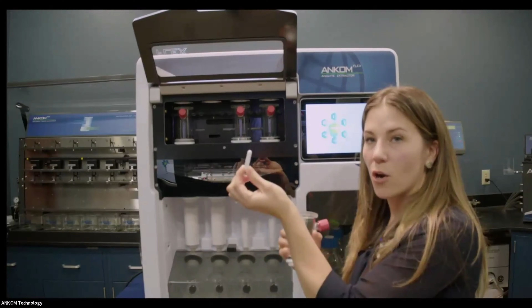Your filter would go in the bottom of this digestion vessel. You would weigh your sample, and just slide it in place. These ports are for, in particular, vitamin analysis. You can add an internal standard. These tops come down and seal the tops of your vessels. And the instrument is going to do a pressure check and make sure you have no leaks, because as I mentioned, everything is inert and done under nitrogen. So the instrument will let you know if there's any leaks.